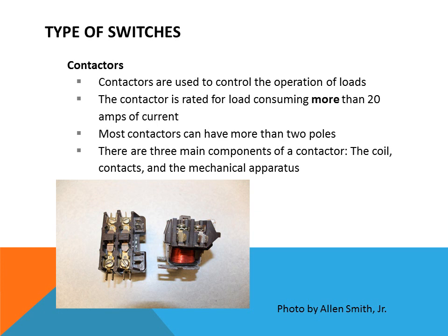So there are many different types of switches, and one type is what we call a contactor. Contactors are used to control the operation of loads. The contactor is rated for a load consuming more than 20 amps of current through its contacts, such as compressors and larger motors. Most contactors can have more than two poles, and these poles are usually normally open.